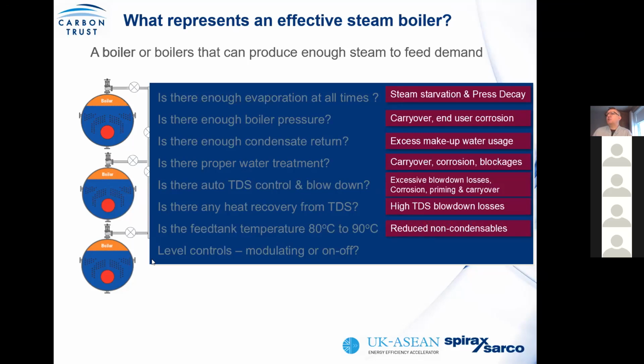Is the feed water temperature at least 80 to 90 degrees? So if you just use a hot water tank, do you maintain a minimum of 80, 90 degrees, or do you have a pressurized deaerator? Because the purpose of the chemicals in your system is that you want to remove what we call these non-condensable destructive gases, which is oxygen and carbon dioxide, from your water. And the best way to remove that is through heat, where chemicals are a last resort. So in other words, you need to ensure that your feed water system is at a correct temperature.